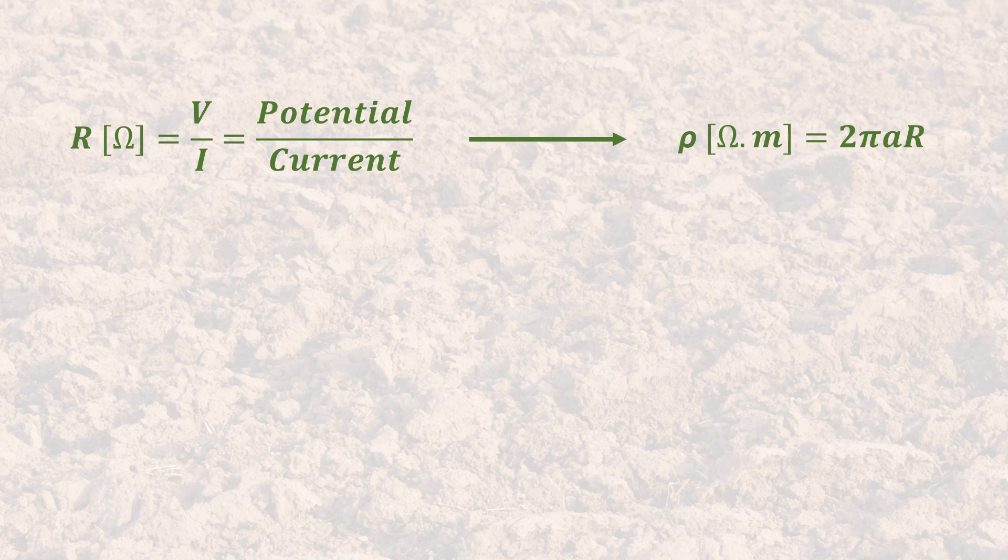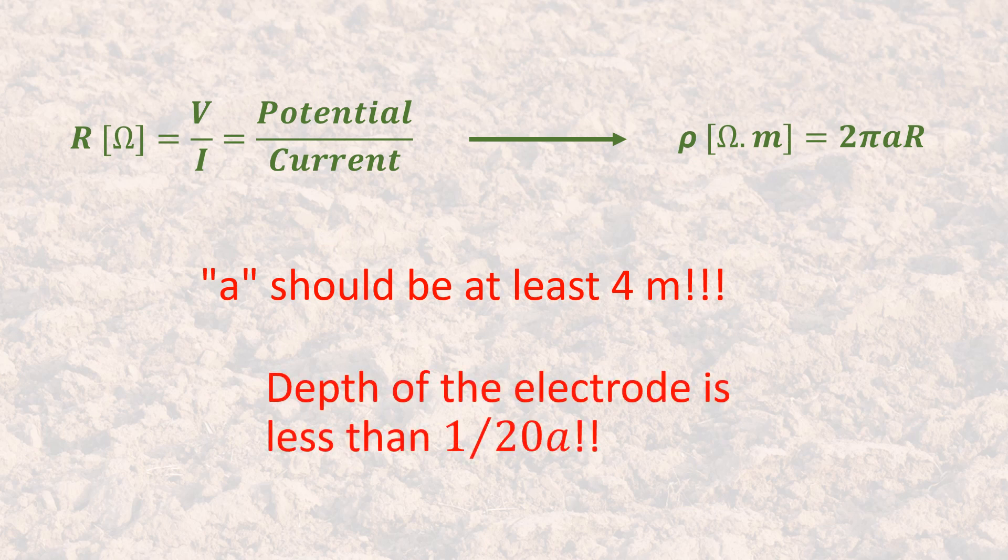We must take into account, in order to apply the equations, that A should be at least 4 meters, and the depth of the electrode should be less than 1/20th A.